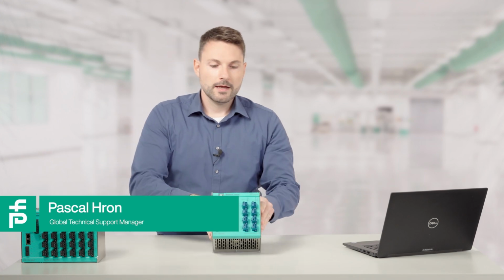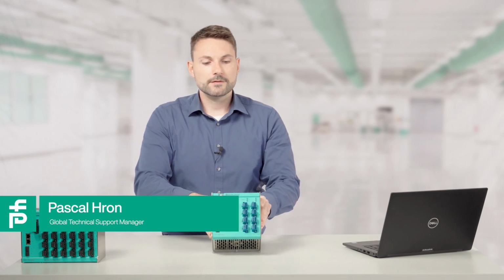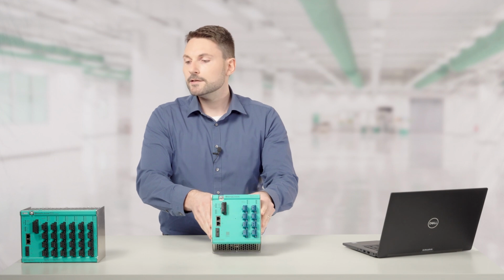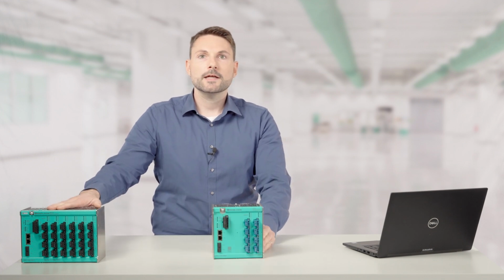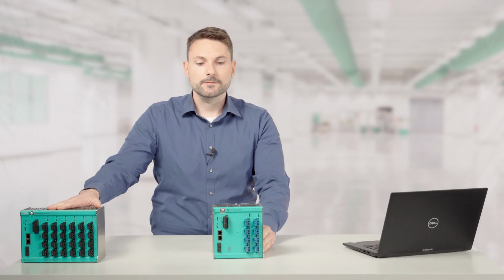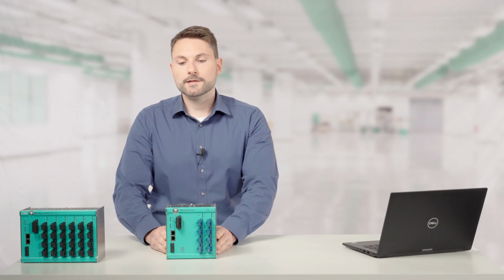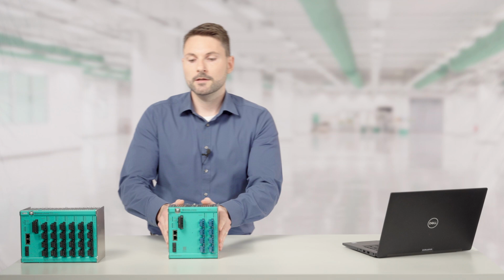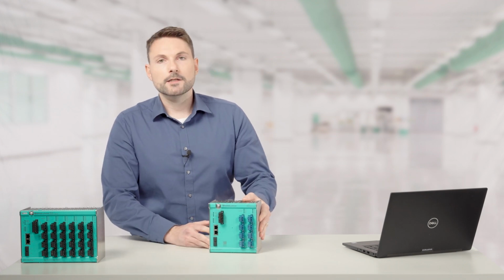One is an 8-port variant of the device for connecting Ex ia field devices, and the other is a 24-port variant for connecting Ex ic field devices. Both devices have a Profibus PA proxy, which means that in addition to connecting Ethernet-APL field devices, they also allow Profibus PA field devices to be connected. The switches are assembled identically.